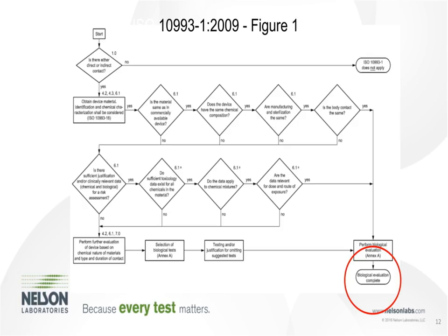The one thing that I can think of right off the bat with this that would be affected is some kind of mask guard for a surgeon. That headband that goes around the skin doesn't have intended patient contact, but it does have intended clinician or user contact, and so that headband now would need to be evaluated for a risk-based biocompatibility approach, where before you may not have been.